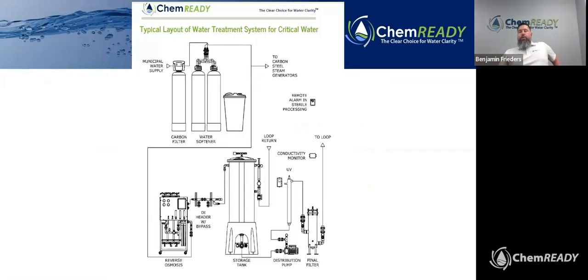If you're unsure of what a typical critical water system would involve, we mentioned it earlier, here it would be a traditional hospital type setup. Okay. In order to get your final critical water quality, you would need some type of carbon filtration that would remove chlorine. A water softener would remove calcium and magnesium ions, amongst some other minimal contaminants. A reverse osmosis system will take out up to 90% of the rest of the ionic contaminants. Some type of deionization, whether it's deionization tanks that you exchange on a monthly or quarterly basis, or an electrodeionization system. All of those pieces would feed to a specialized storage tank. The storage tank, per the standard, must be cone bottom, and it also must have some type of air filtration, usually a HEPA filter, to prevent any airborne contaminants from coming into your system.